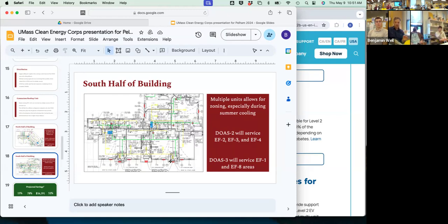Remember, in winter or in heating mode, the primary source of heat is still those unit ventilators. It's just that now they're fan coil units, so they can operate with a maximum water temperature of, we calculated, 115 as the maximum required water temperature. Because they're not warming up the outside air, they're just recovering what's lost. All they're doing is handling the return air within the classroom. They're just a fan coil unit now, but they're too big because they don't need to do any outdoor air. So that's why that existing system can now do the whole deal.